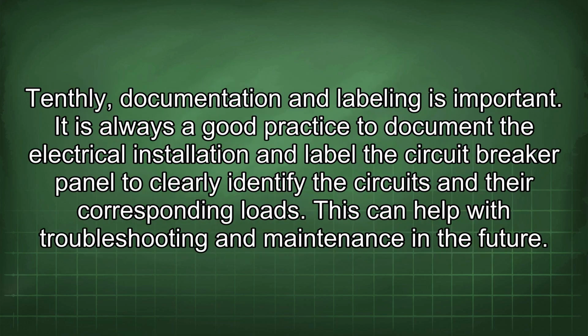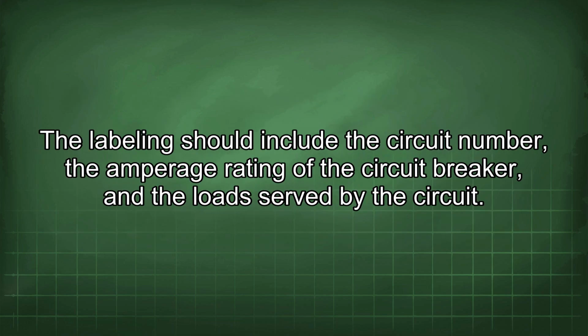Tenthly, documentation and labeling is important. It is always a good practice to document the electrical installation and label the circuit breaker panel to clearly identify the circuits and their corresponding loads. This can help with troubleshooting and maintenance in the future. The labeling should include the circuit number, the amperage rating of the circuit breaker, and the load served by the circuit.